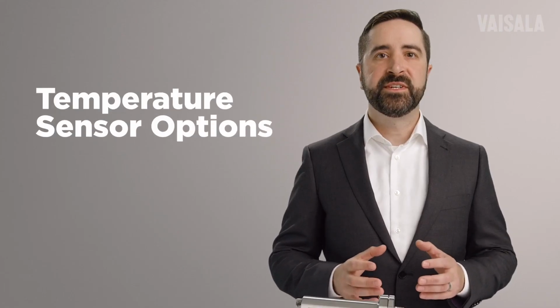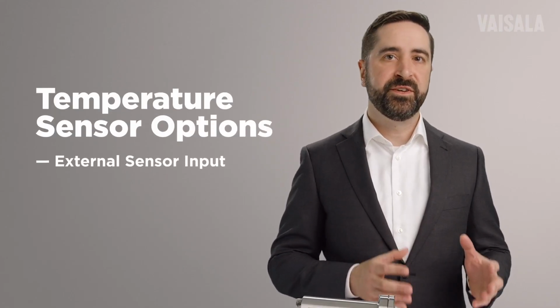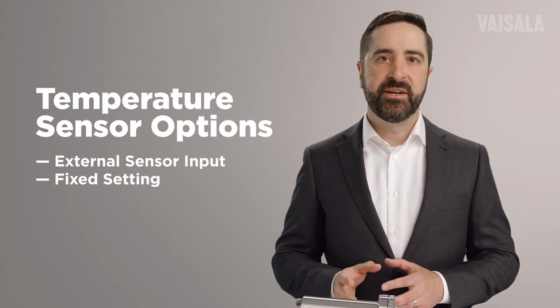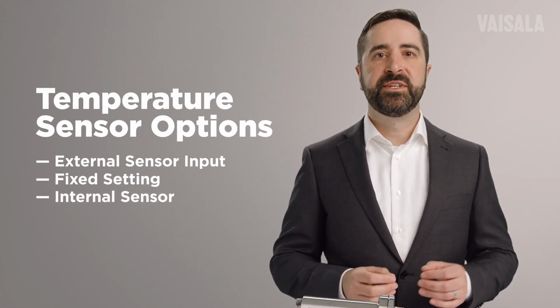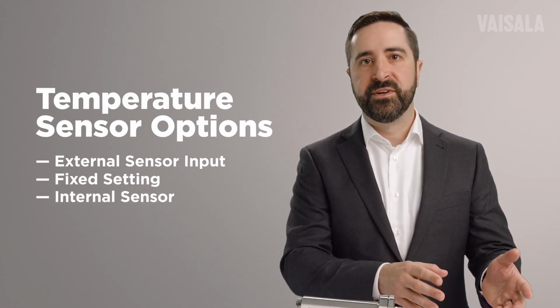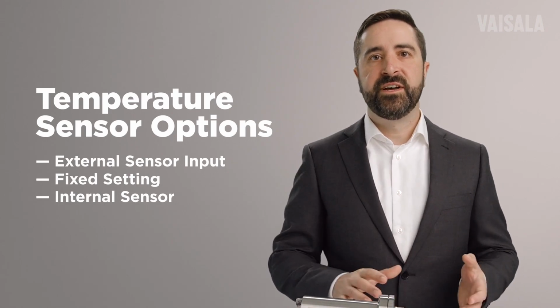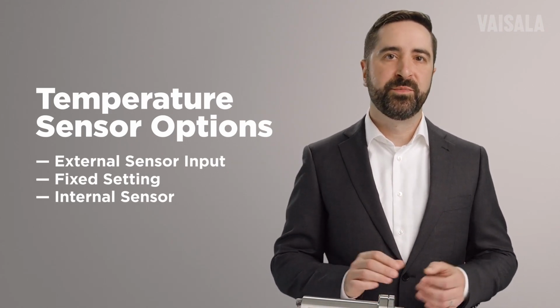The MGP 260 series can accept a temperature sensor input or a fixed temperature setting, but we recommend customers use the included internal temperature sensor for active measurement. This allows for the temperature reading to be closest to the point of measurement. When it comes to the pressure compensation, this can be achieved two different ways.